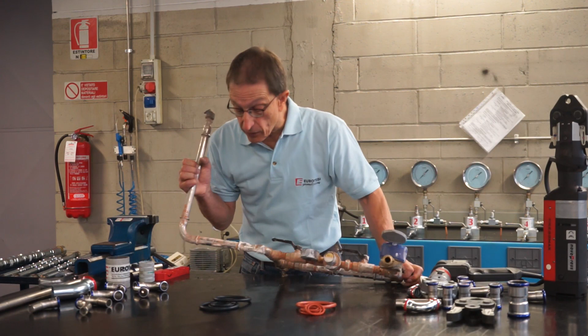In construction sites, we must keep these substances from coming into contact with the pipes before they have been adequately insulated with specific closed-cell materials. It would be a shame if a state-of-the-art installation like this one, which could remain operational for over 20 years, had to be replaced because it was contaminated with aggressive construction materials. With time, these substances can create holes in the steel and, therefore, leaks.